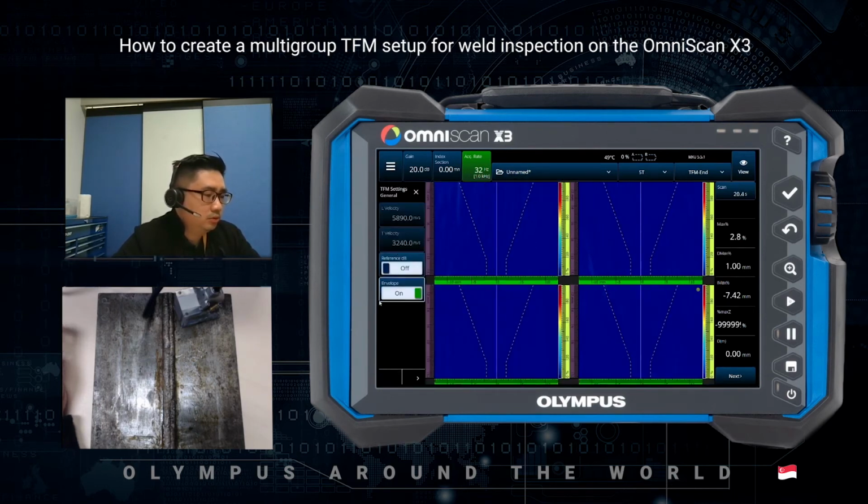Okay, so envelope is on. Great. The voltage, let's put high voltage 115. So it's global for this guy. And we can see the TFM zone settings. It's exactly like what we defined earlier. You can of course modify them. And the resolution is 0.17 for all four groups.